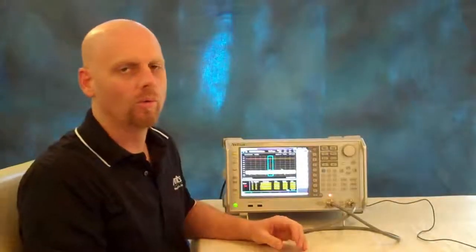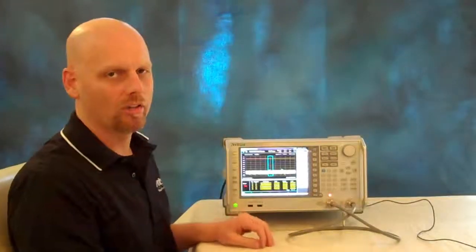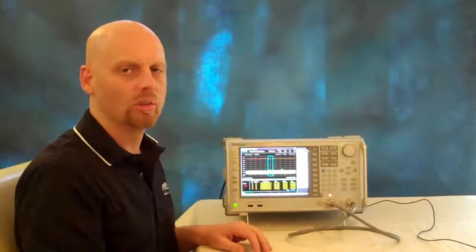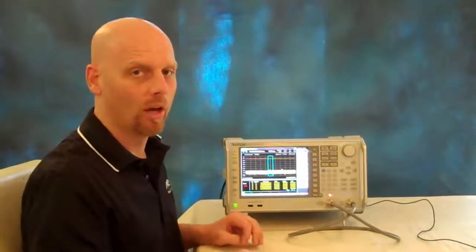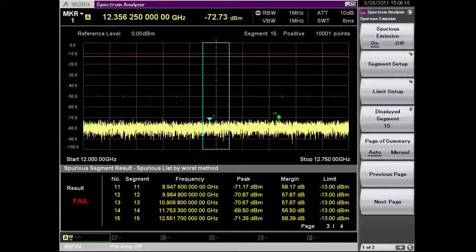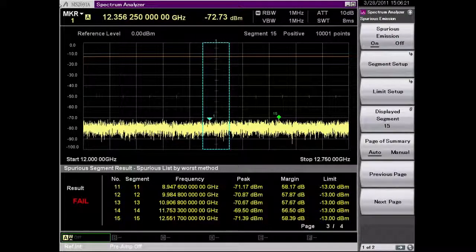Now I'd like to show how powerful this application can be for doing a simple harmonic test. I'm going to test my fundamental through the fourth harmonic. I've already set this measurement up in advance in order to save time.